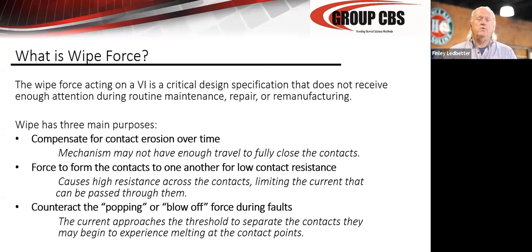Let's talk about wipe force. I want to talk about some things today that people don't normally consider. Wipe force is the amount of pressure in all circuit breakers, vacuum, air, oil, anything. They have a wipe force spring that maintains pressure and holds the contacts together. If it's an air breaker, it holds it closed. If it's a vacuum breaker, it's essentially holding pressure.